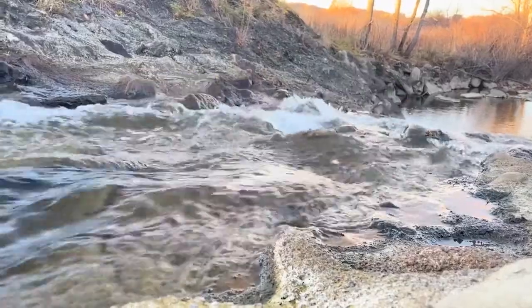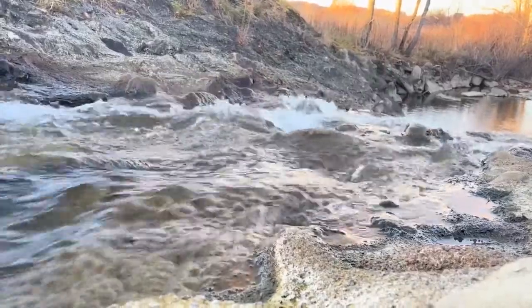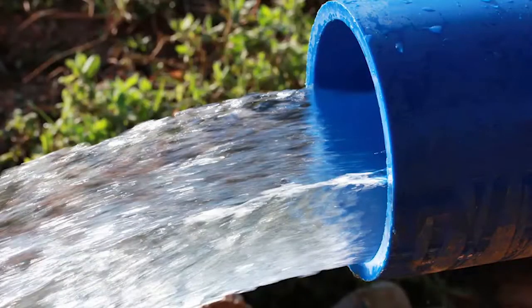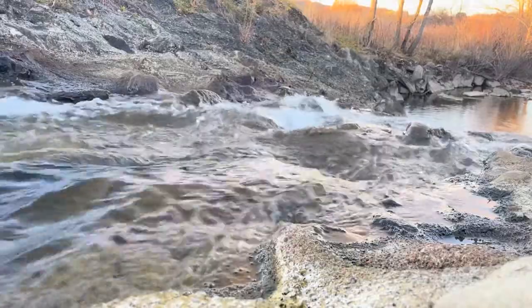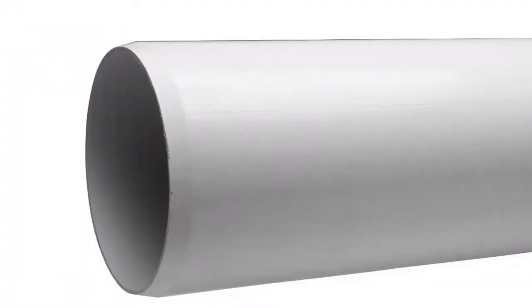Drainage pipe must be of the right size to have a liquid flow of about 50% of the pipe diameter, meaning that the flowing water inside the pipe must have a depth equal to 1/2 of the pipe diameter. 4. For instance, if the pipe is 100 mm in diameter, the water flow inside the pipe must have a depth of about 50 mm to attain the scouring action.